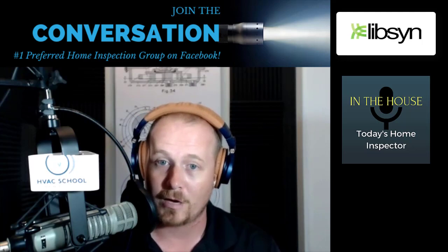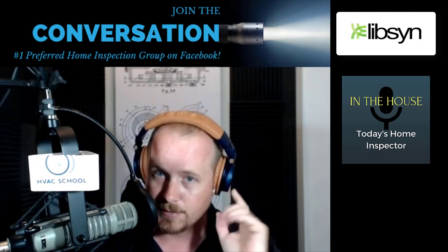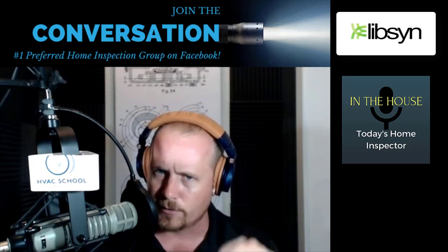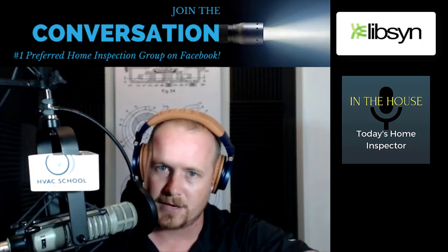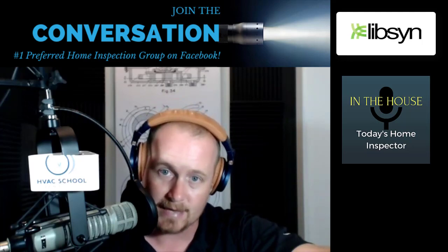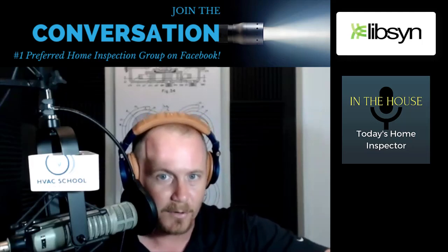That's what I do. When I walk up to an air conditioning unit, I'm listening to hear, is it making any abnormal noises? Am I hearing a compressor going on and off erratically? Am I hearing bearing failure? I walk up, I throw my hand over the condenser, because that heat that's coming out of the top of the condenser, that's the heat that came from inside. So if you don't feel a decent amount of heat, then you want to start looking.